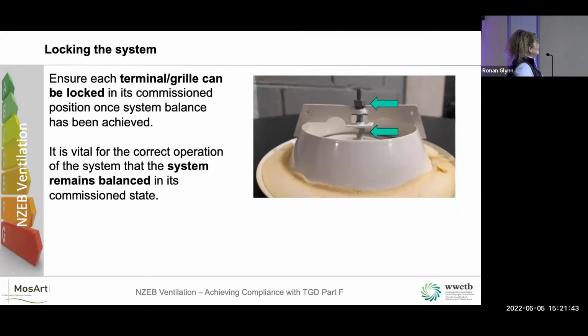Locking the system, really, really important. So once you've commissioned the system, you have to ensure that the terminal or grill or diffuser or whatever you want to call it has been locked in position once the commission has been achieved. Now do this before you commission it, else you have to take the whole thing off again. So you take the diffuser out, you put a little nut on it there, and you put another one on the top.